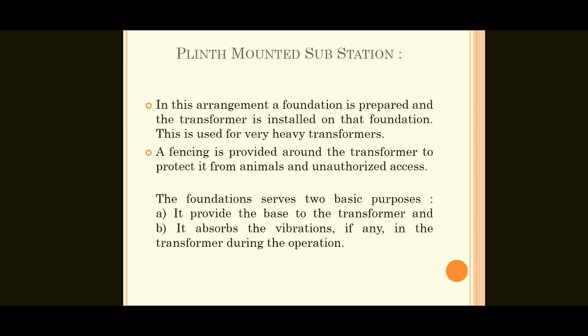Next one, plinth mounted substation. In this arrangement, a foundation is prepared and the transformer is installed on that foundation. This is used for very heavy transformers. A fencing is provided around the transformer to protect it from animals and unauthorized access.